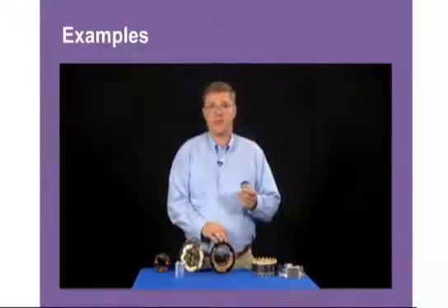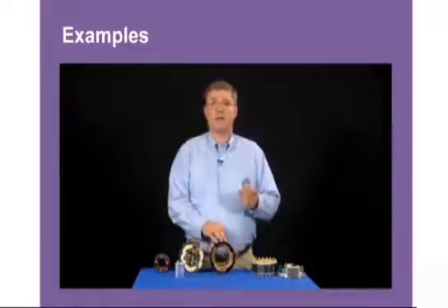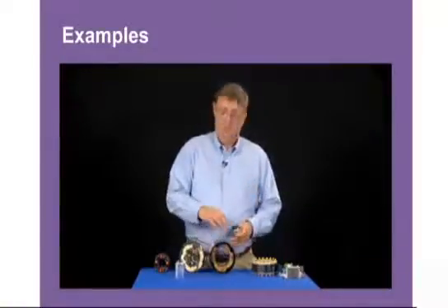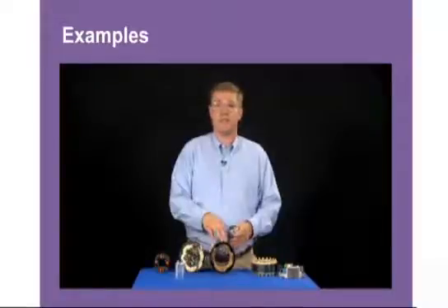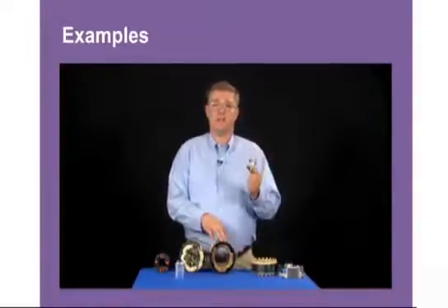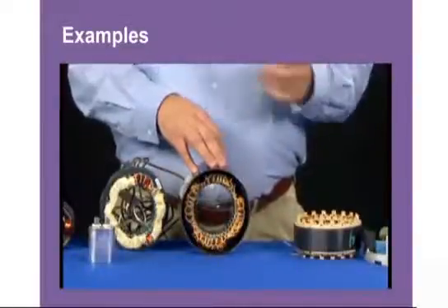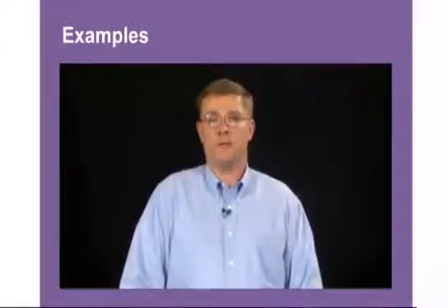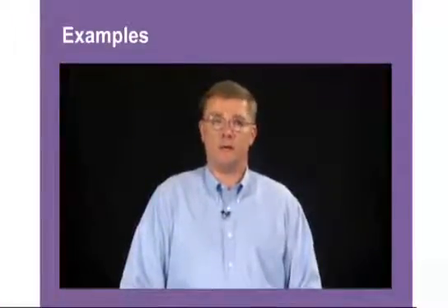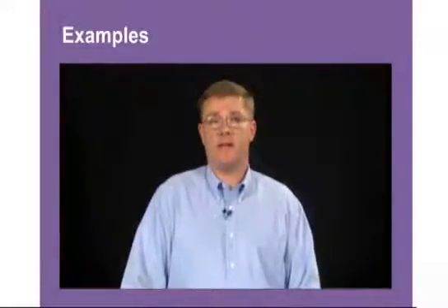The third type of split phase motor is a capacitor start, capacitor run motor. This type of motor has a capacitor in the start circuit and the run winding, and again still has a centrifugal switch. This type of motor should never have a speed control put on it. The most efficient motor in the market is a three phase motor. These motors have three sets of windings that pull on the rotor, making them one of the more efficient motors. One easy way to identify a three phase motor is the number of leads exiting — either a 9 or 12 wire configuration. These are typically in a commercial application.